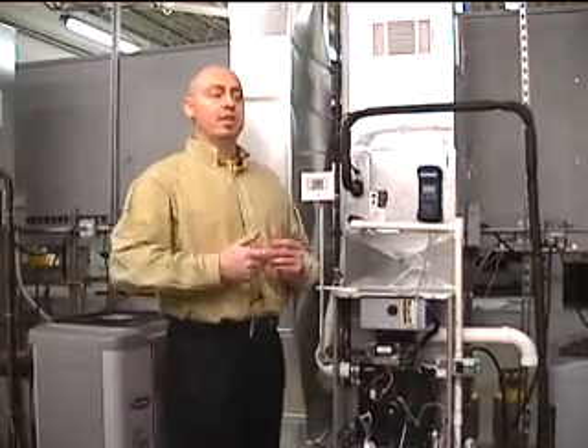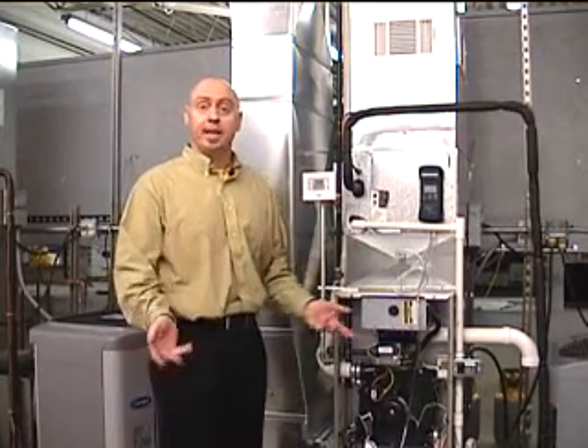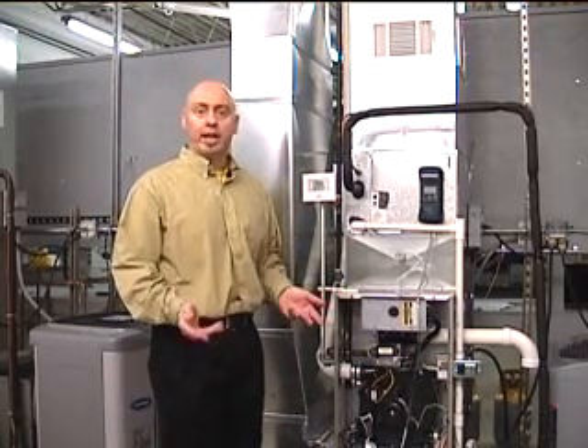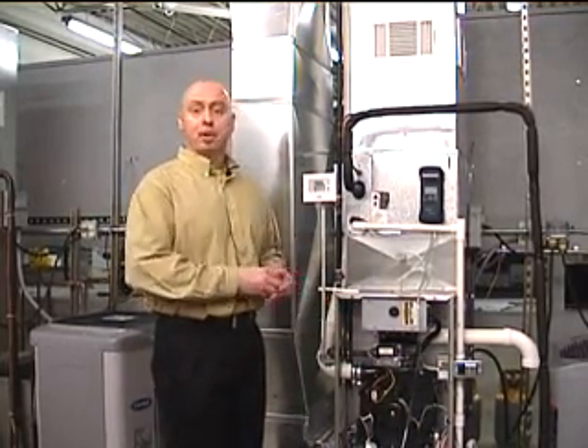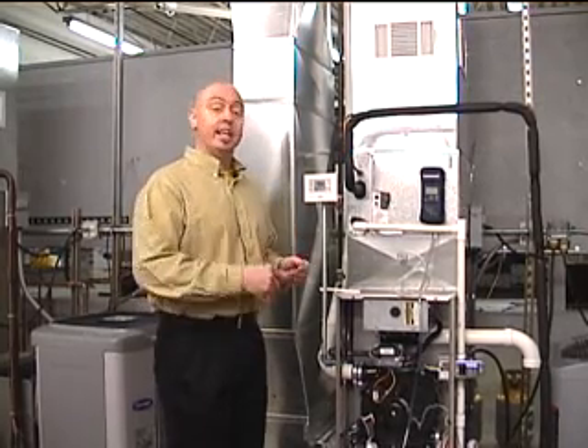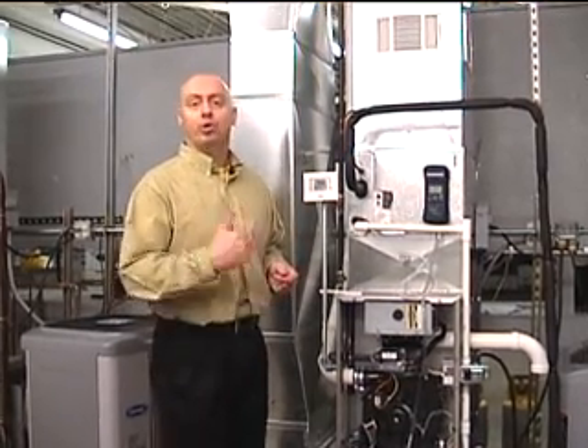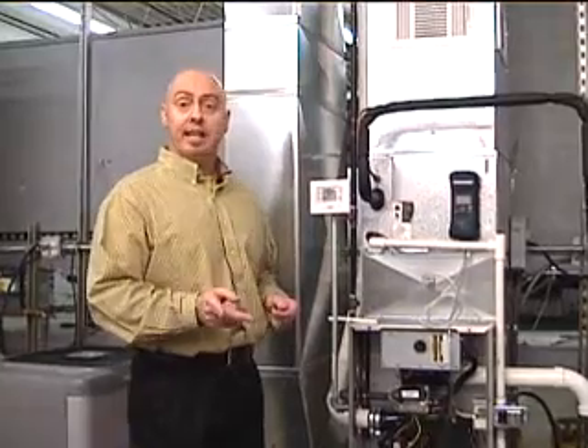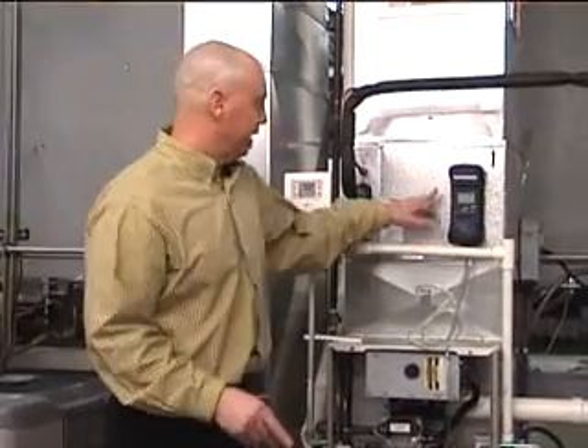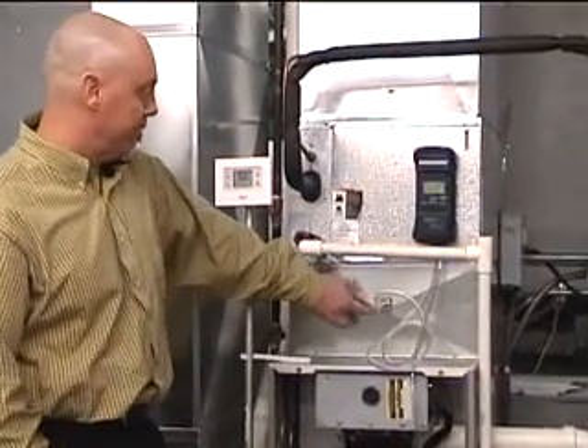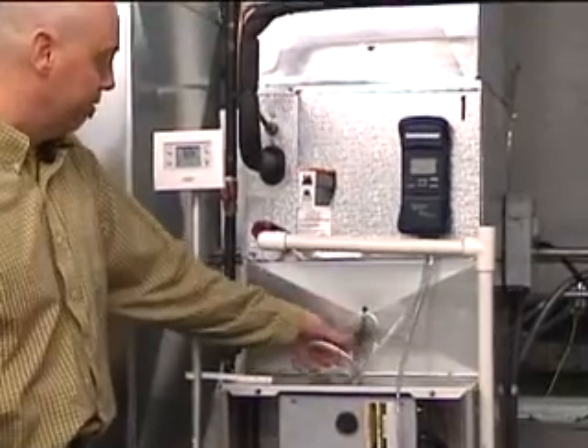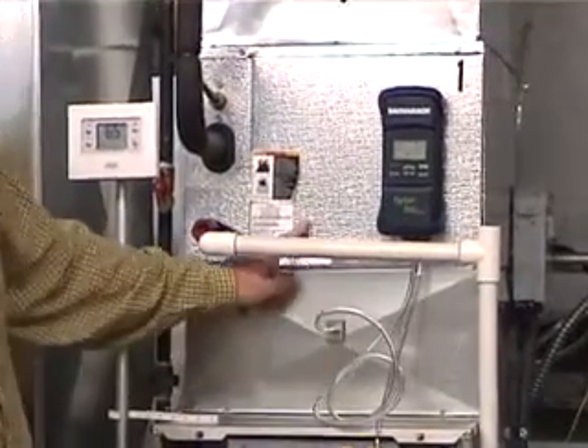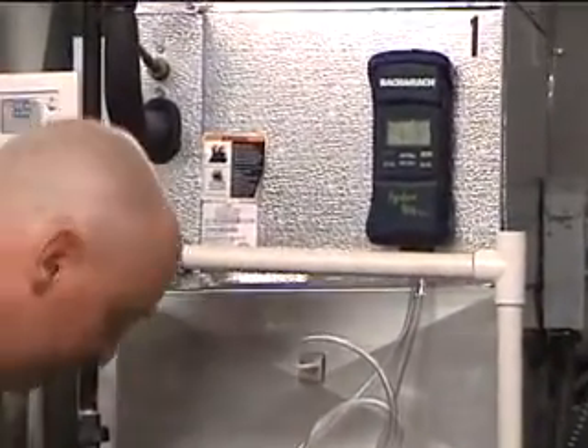Now what I wanted to show you was a very common mistake that technicians make out in the field when measuring total static pressure. I've seen some of the most experienced guys make this mistake, and it can give you a false positive reading. So I want to show you how to avoid that. This is my actual static pressure right now. And again, I'm taking my readings between the coil and the furnace, and between the filter and the furnace. And that is the correct way to do that.